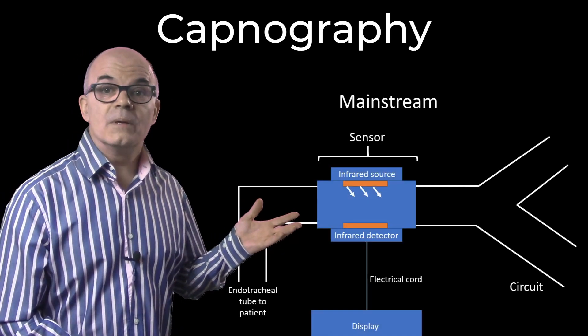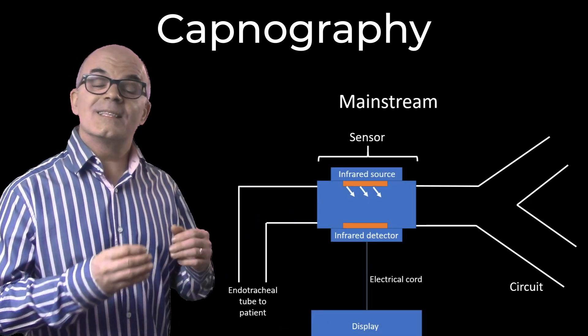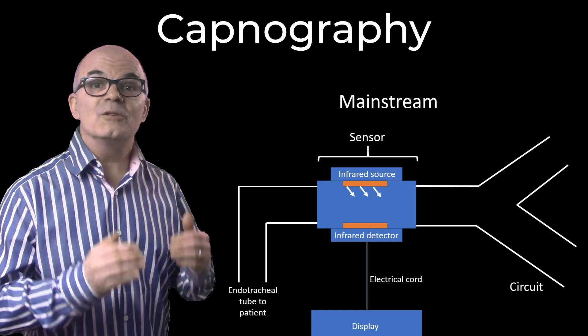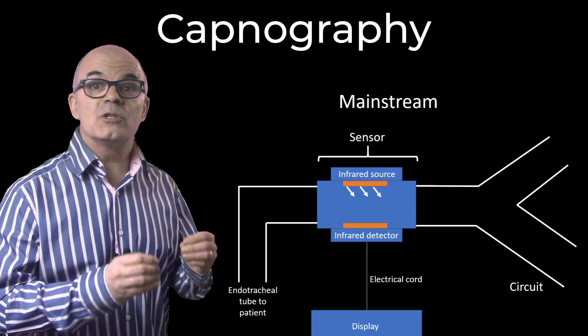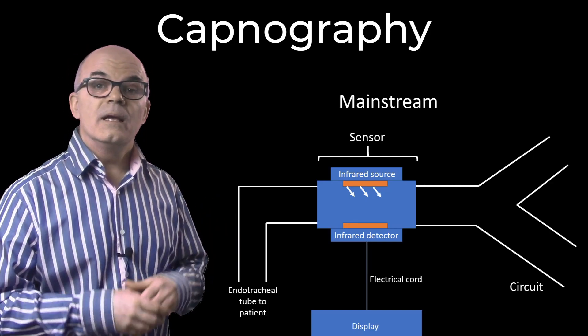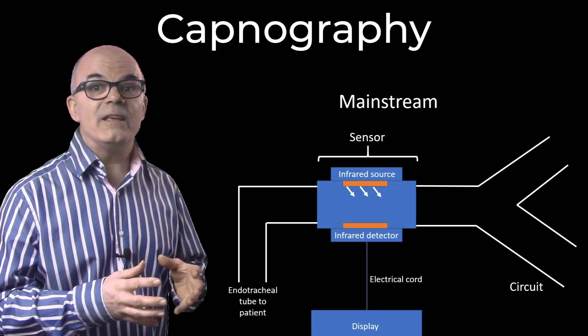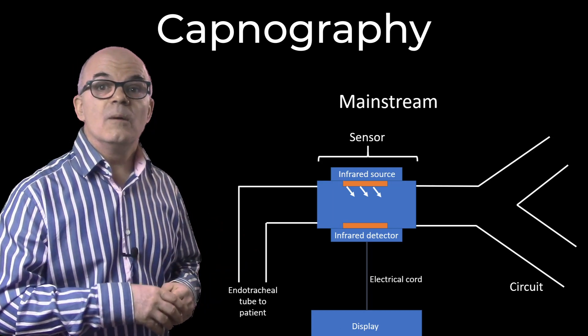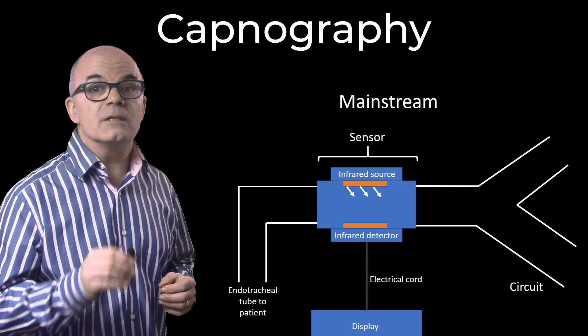Types. Mainstream. The CO2 detector sits in line with the endotracheal tube and detects the CO2 at that point. These can be rather bulky and heavy compared to the alternative, but they do give a more immediate reading.